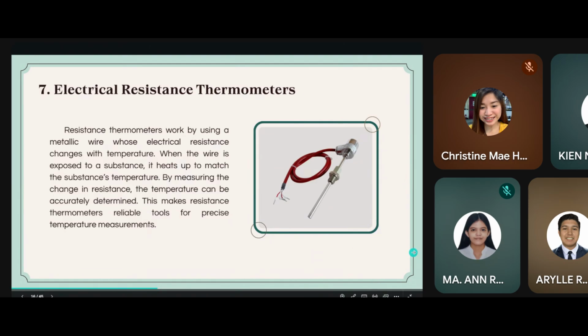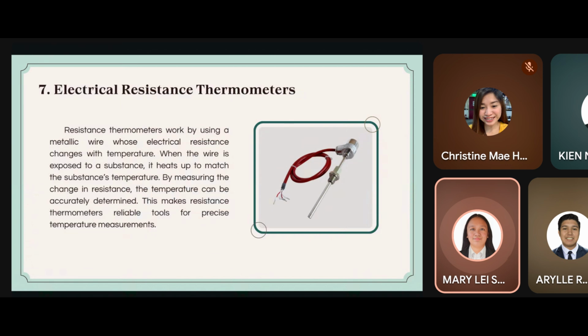For the next instrument, you have electrical resistance thermometers. Resistance thermometers work by using a metallic wire whose electrical resistance changes with temperature. When the wire is exposed to a substance, it heats up to match the substance temperature. By measuring the change in resistance, the temperature can be accurately determined, and this makes resistance thermometers reliable tools for precise temperature measurements. Next po.